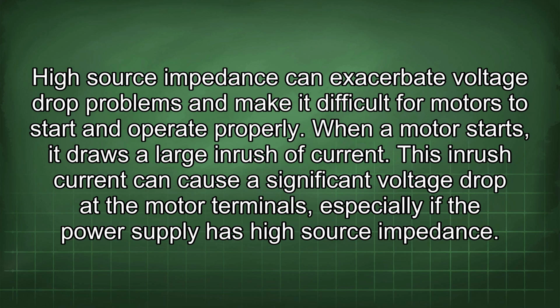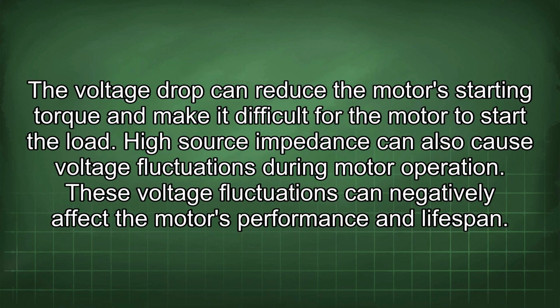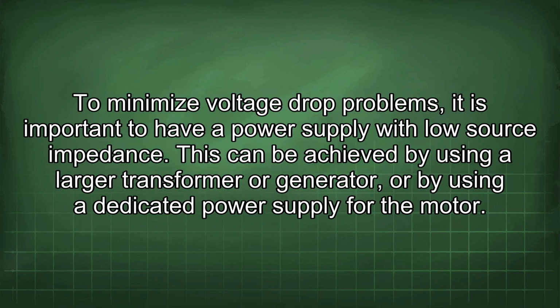source impedance. The voltage drop can reduce the motor's starting torque and make it difficult for the motor to start the load. High source impedance can also cause voltage fluctuations during motor operation. These voltage fluctuations can negatively affect the motor's performance and lifespan. To minimize voltage drop problems, it is important to have a power supply with low source impedance.